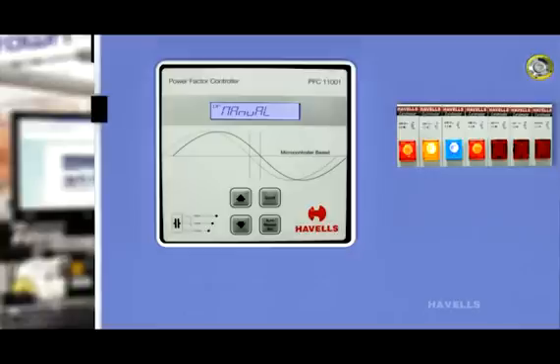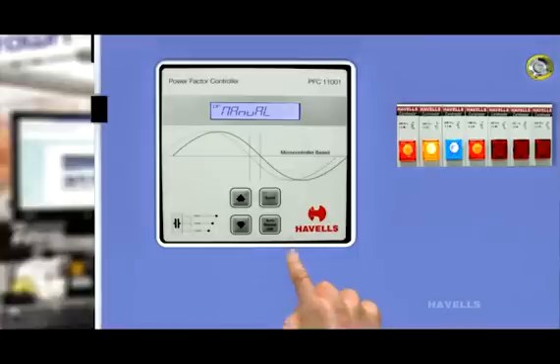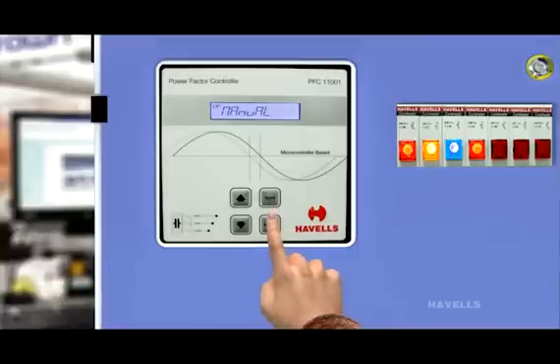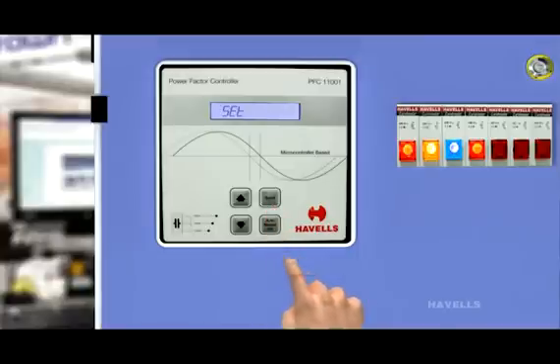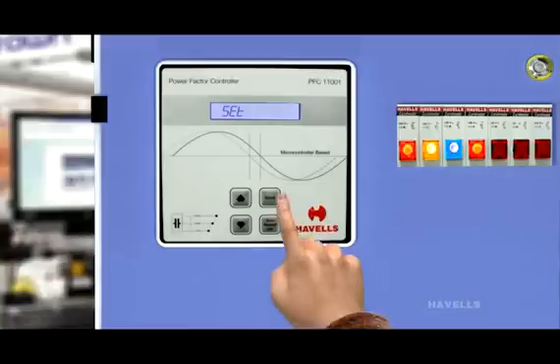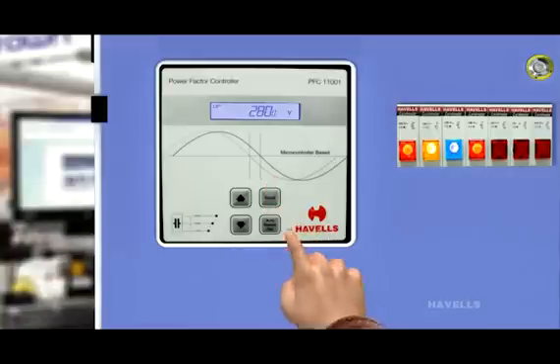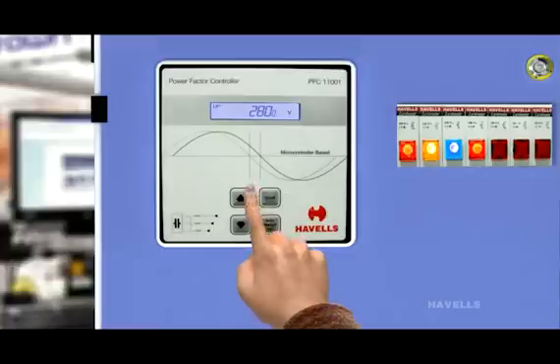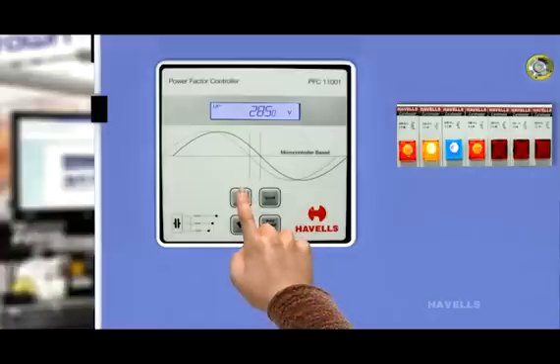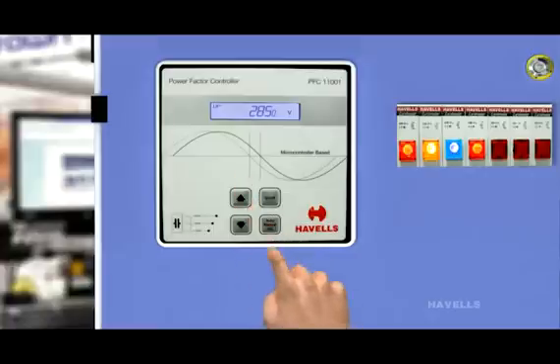then following steps have to follow. Press auto manual set switch till display shows SET. After that, press scroll switch that shows upper voltage threshold on LCD. By default, it is 280 volts. Through up and down switch, the voltage can vary from 240 volts to 300 volts.